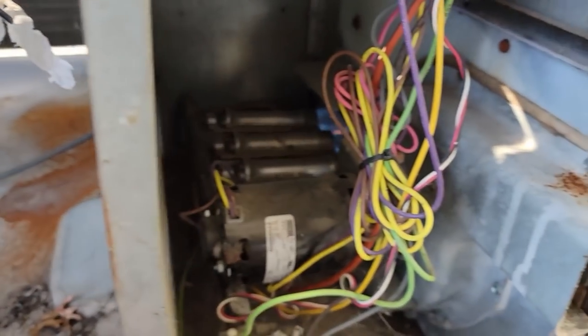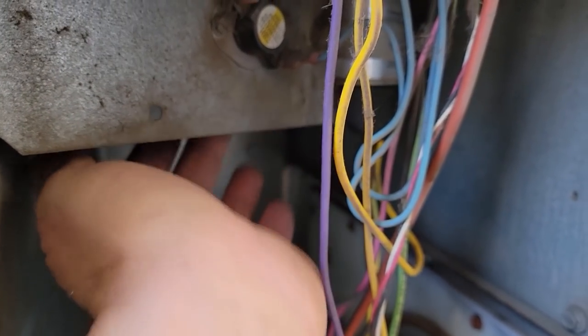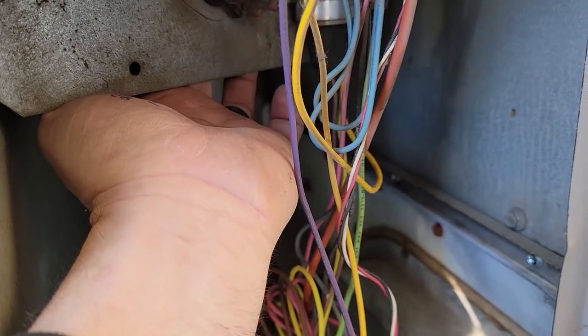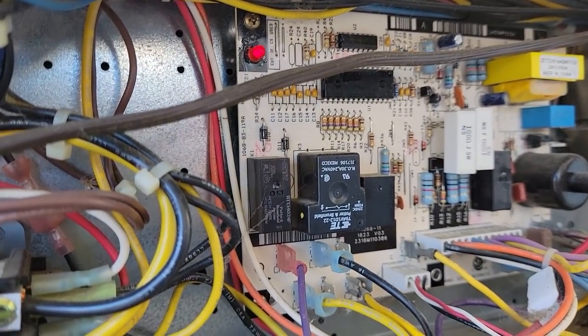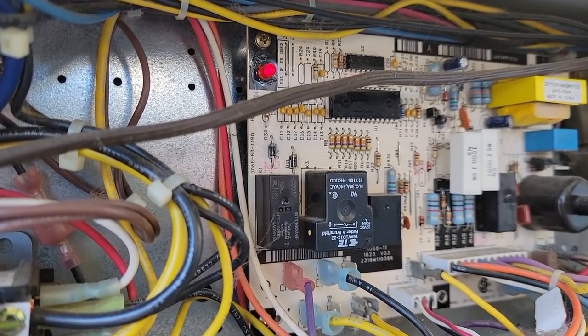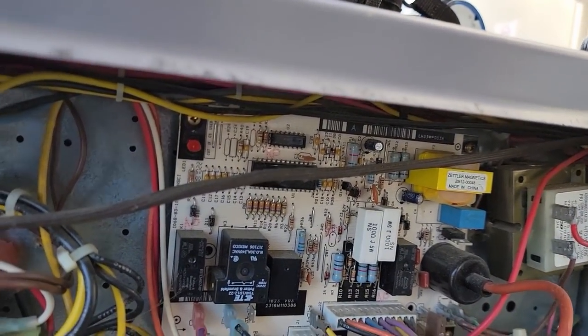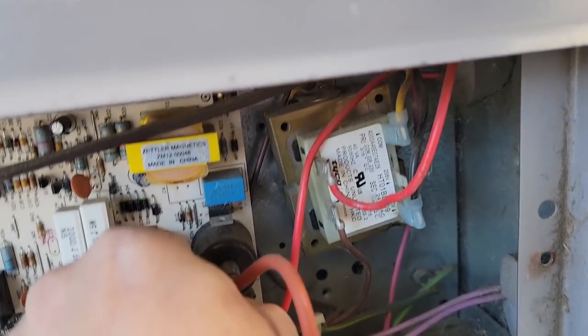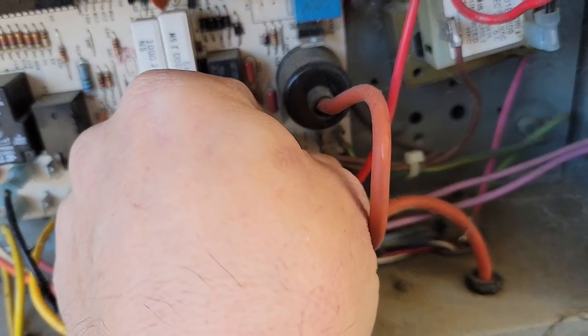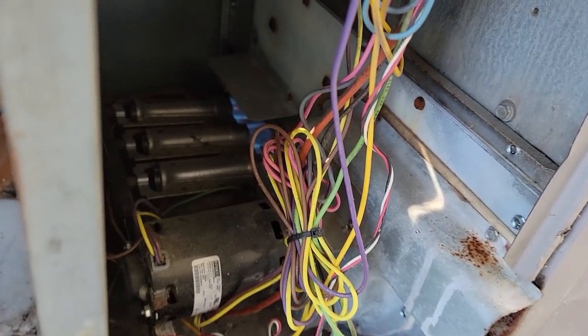I'm not feeling any heat rollout here. Watch this — if I touch the back side of that, just barely touch it, there it goes — trips out. When it trips out it locks into a hard lockout. It should be number seven: one, two, three, four, five, six, seven. The only way to get it to reset is to kill power and start over again.